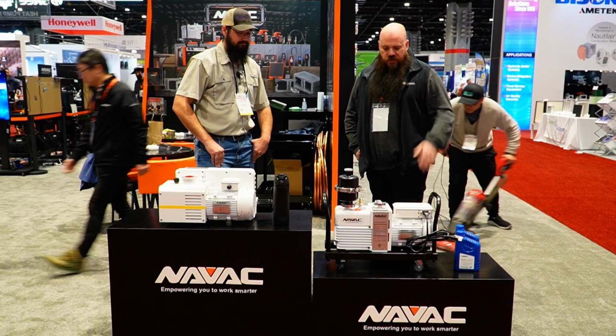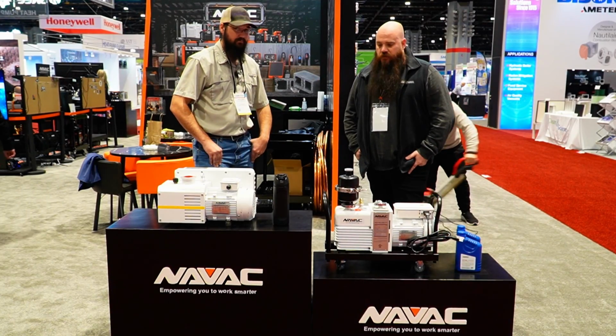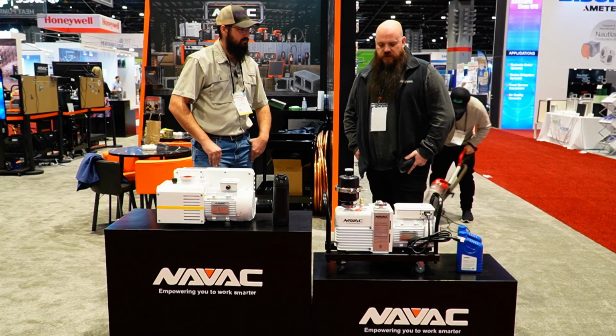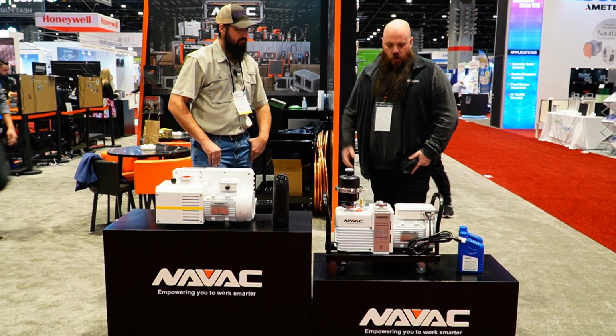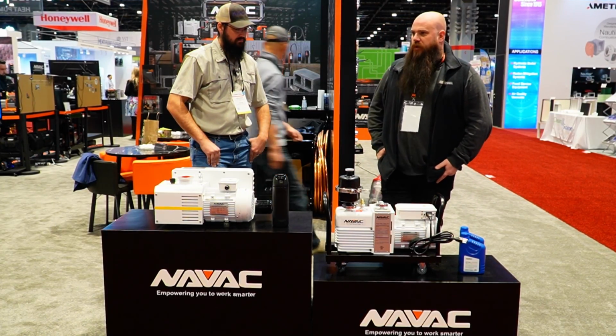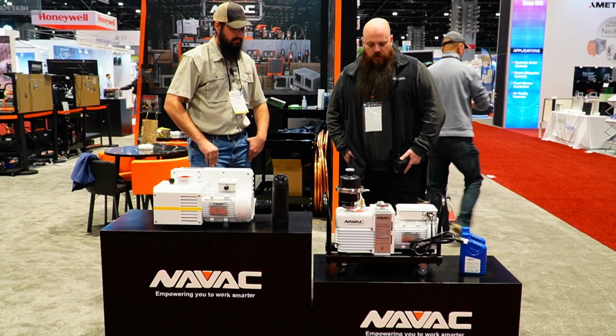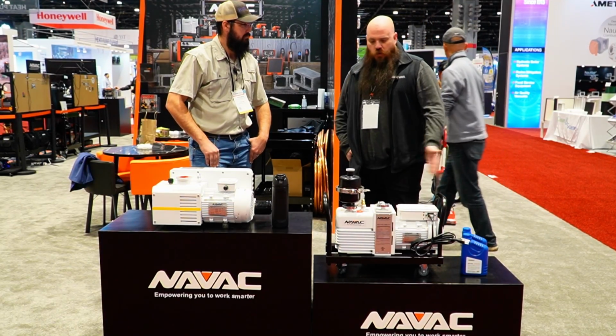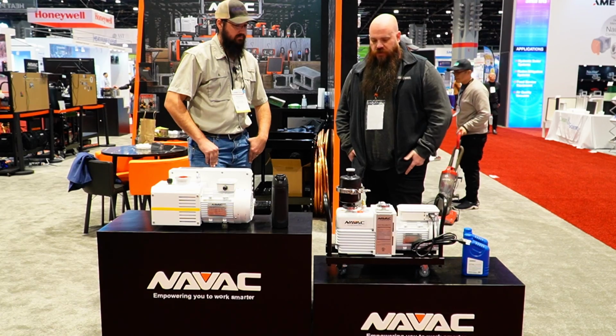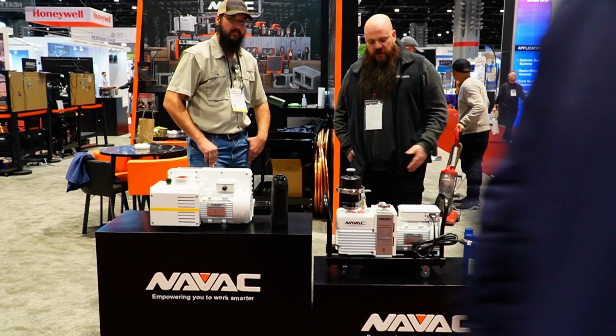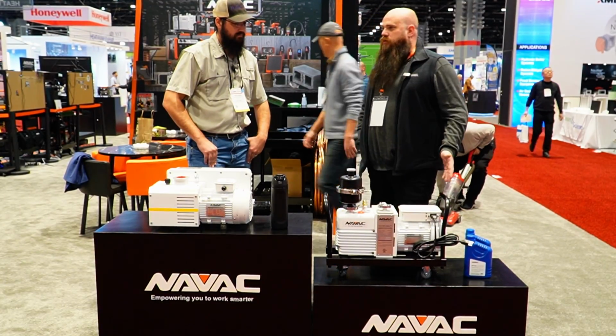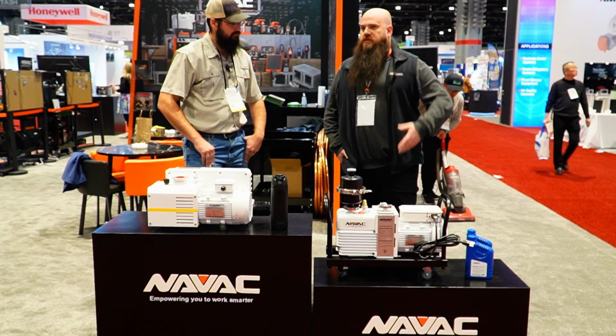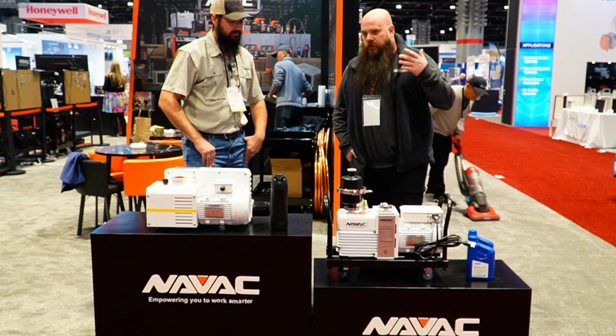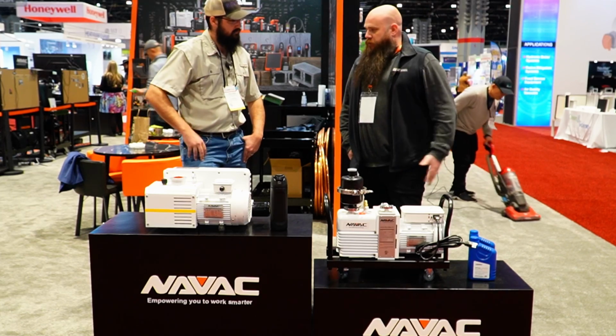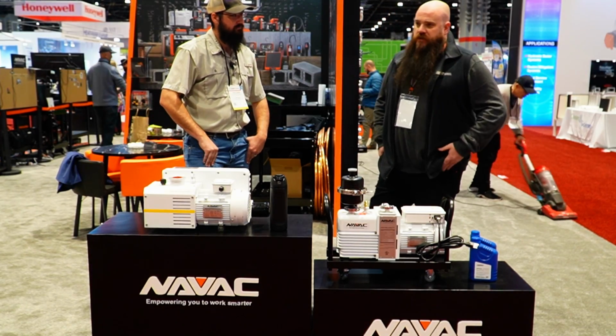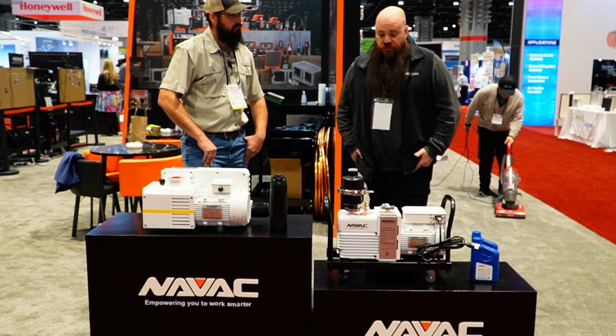So we want our technicians to get the most out of an investment like this. Obviously, it's going to cost a little bit more than your typical vacuum pump that you do residential work with. So we need to support it with the right products that enable it to do what it needs to do. To me, it's the same argument as using proper hoses - not using proper hoses or proper hardware is not good, it's going to derate your pump, it's going to derate your investment, which only hurts you.